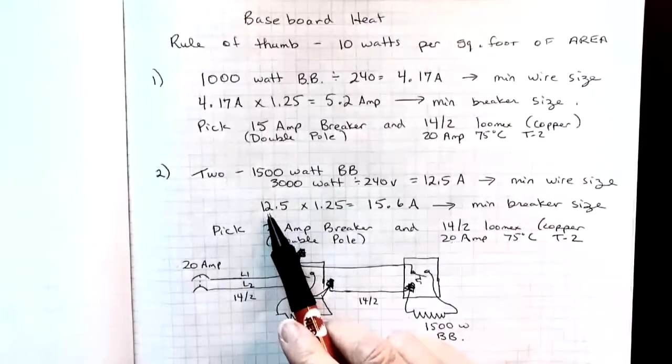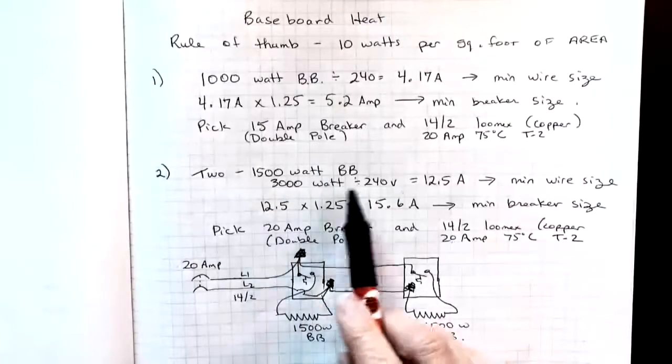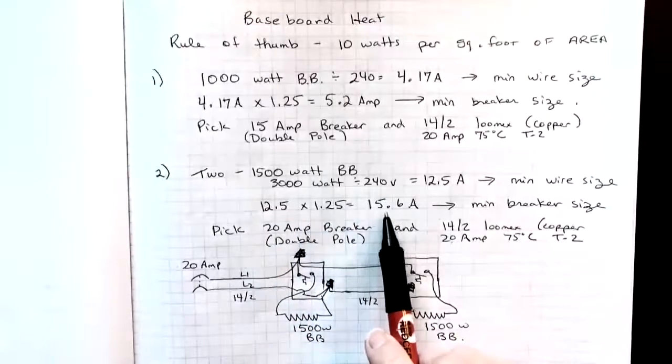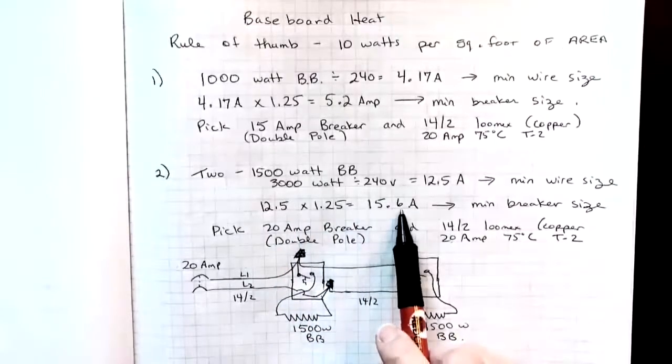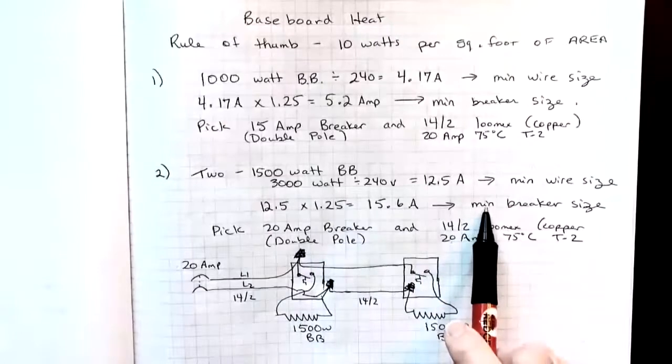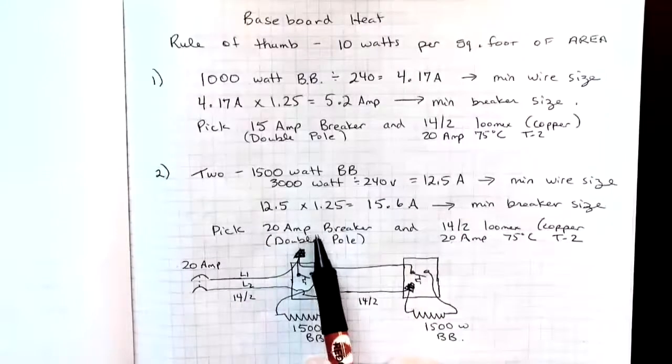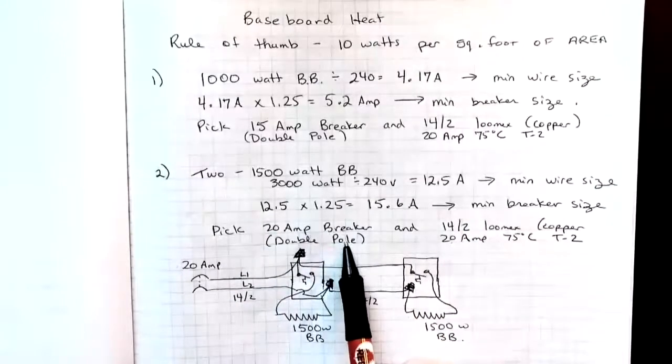Then to pick a breaker size, I'll take that 12.5, multiply it by 125 percent, gives me 15.6. That's going to be my minimum breaker size. So I choose the next size available and it's 20 amp breaker. And that's going to be a double pole.